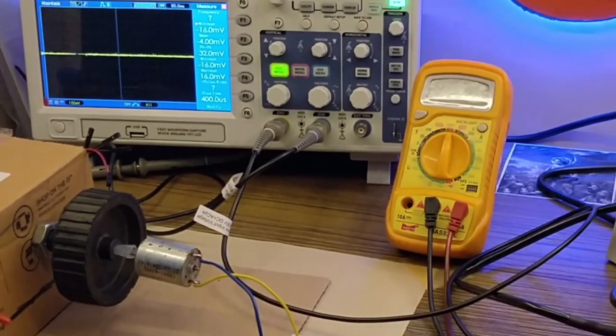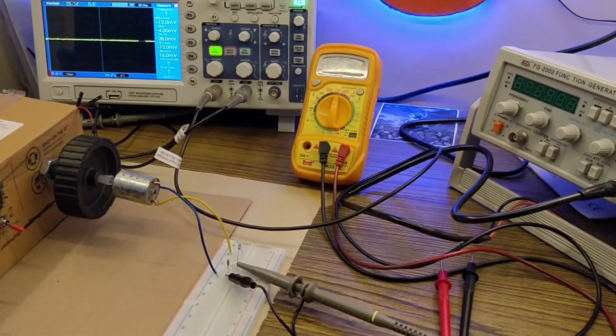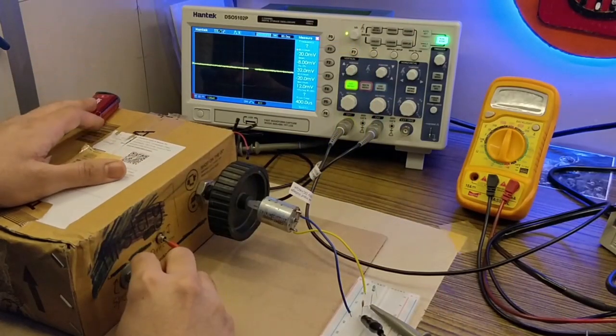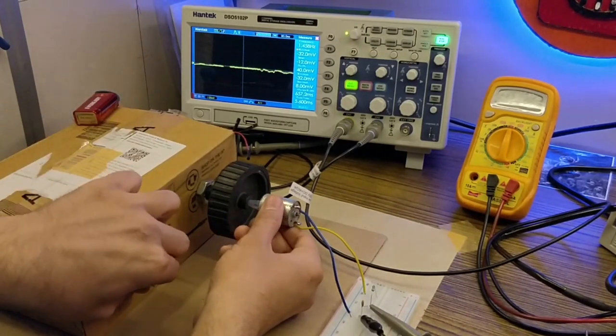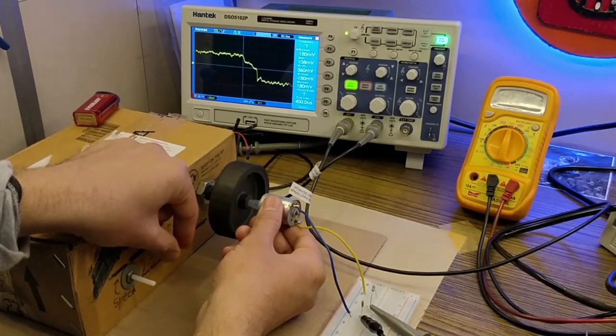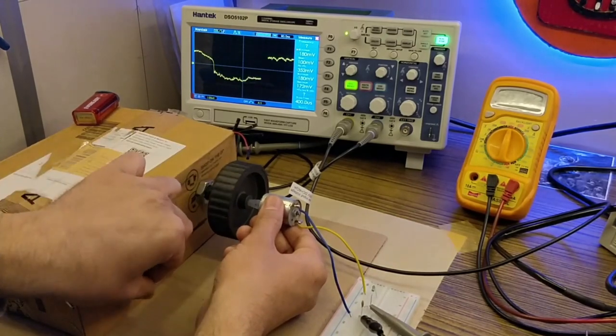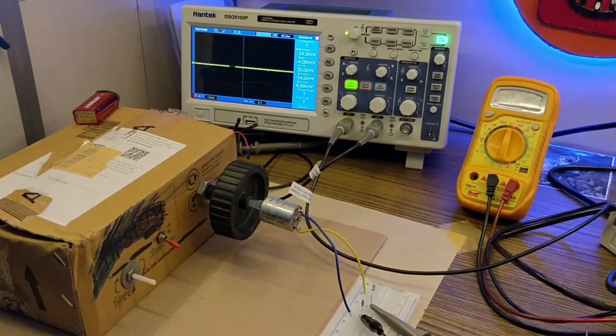Clearly the filter has done its task and I am getting around 160 millivolts of reading for full rotation speed of the motor. But the problem is that I do not know the value of KT. So I cannot calculate speed directly from this. I need to do calibration of some sort. So this cannot give me the absolute value of speed. It can only give me a voltage proportional to the speed, and calibration has to be done to get the absolute value of speed. One good thing about the tachogenerator method is that it's able to give me the speed as well as the direction of rotation of the motor. Remember this, we'll be thinking about this later in the video.